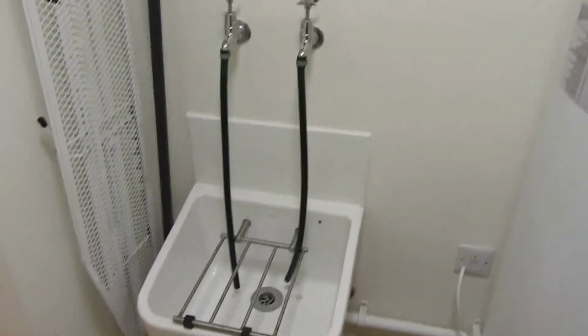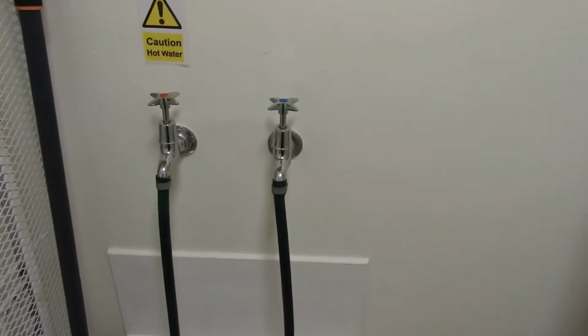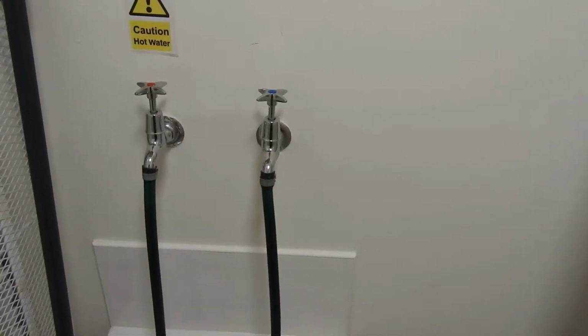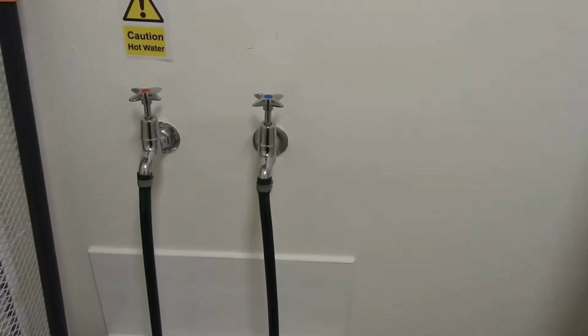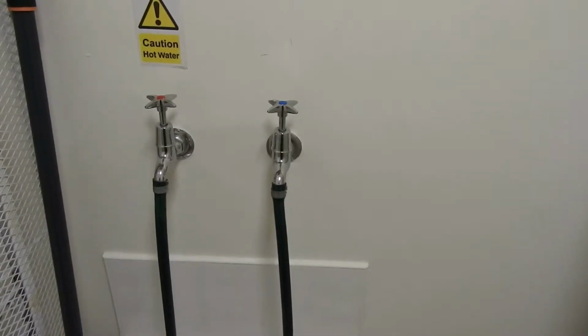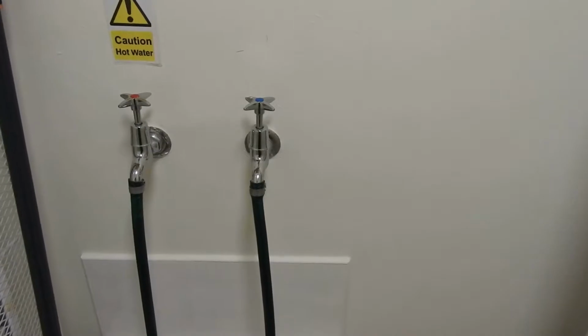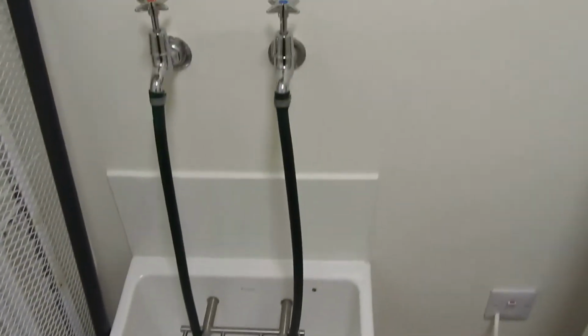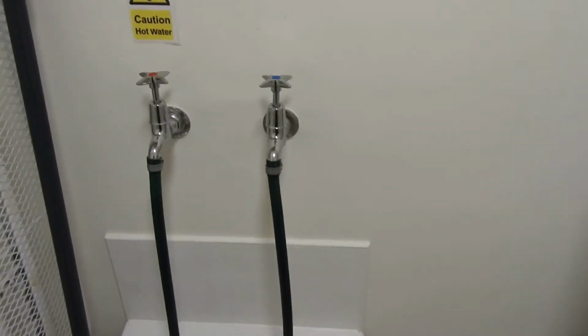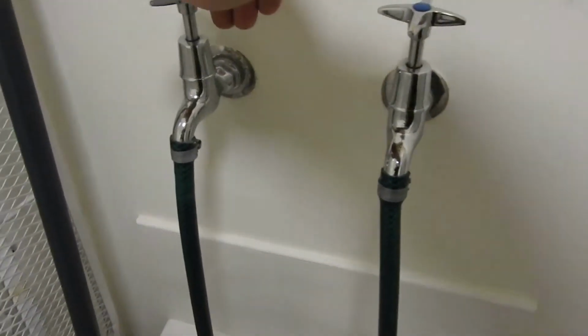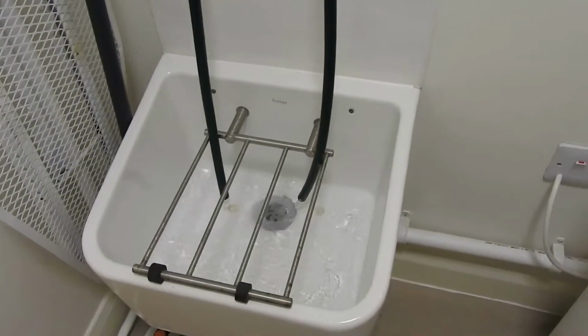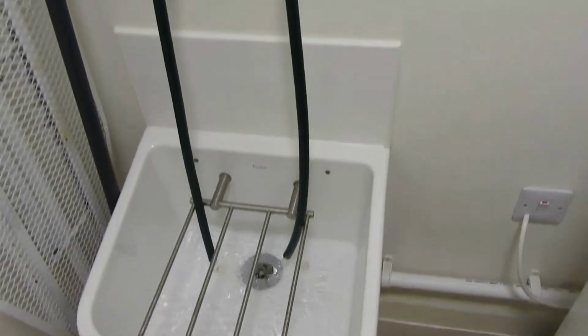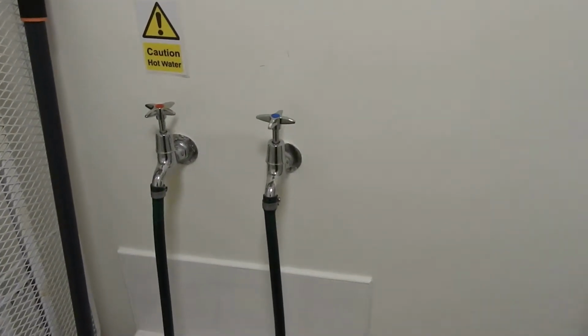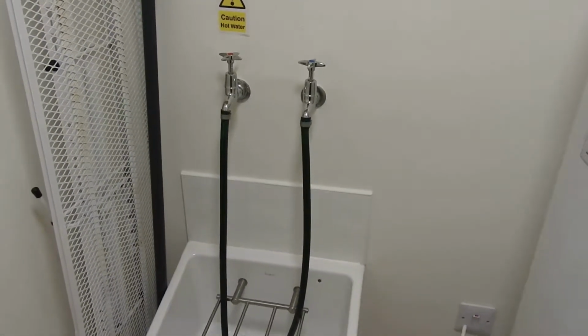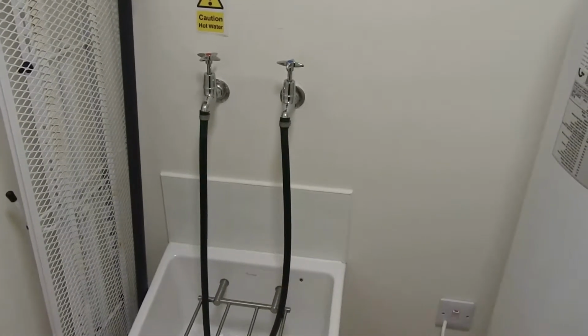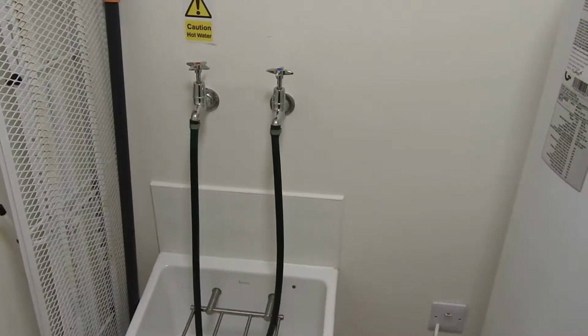and a sink. Now the first unusual thing you notice is that I've got some hose pipe attached to these two taps, and the reason for that is that Legionella is transported in fine aerosols of water, very small droplets. Now if you turned those taps on and the water then flowed into that sink, because of the drop there, the droplets went everywhere. Now that we've added these hose pipes, no big droplets, very little aerosoling. So it's things like this you might want to look out for when you're wandering around your building. Is there anything you can do to lessen the risk of aerosol production? It's called risk assessment. You're doing it all the time, of course.